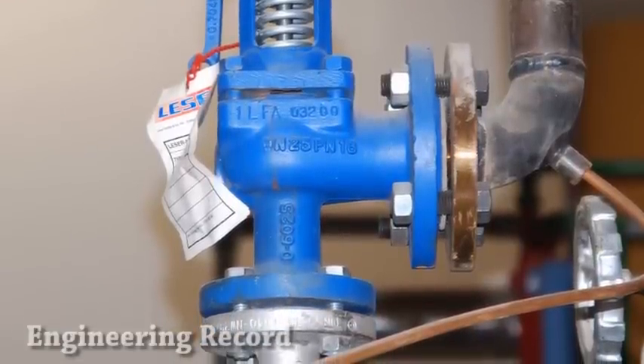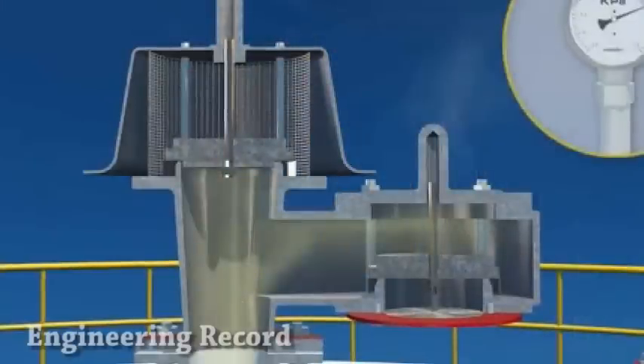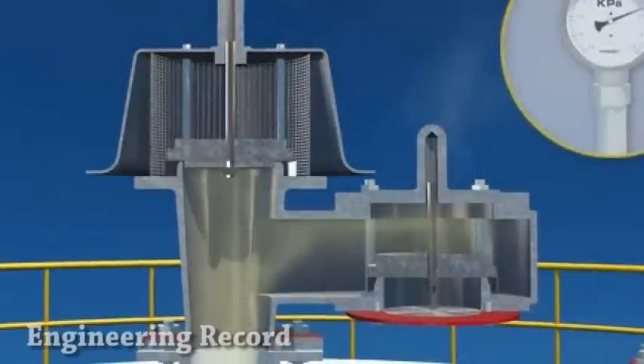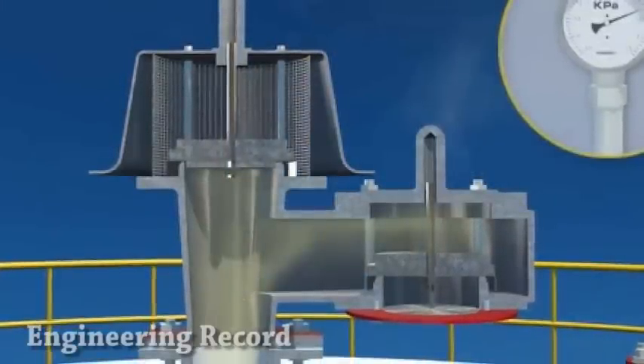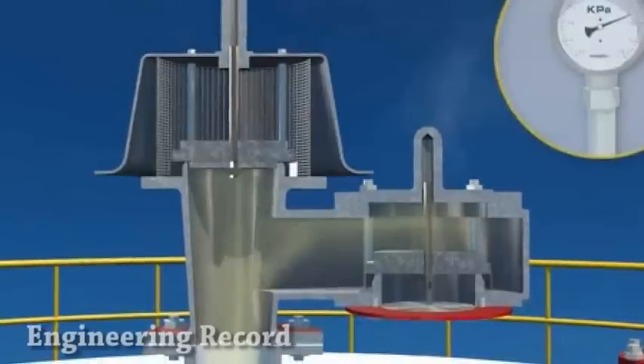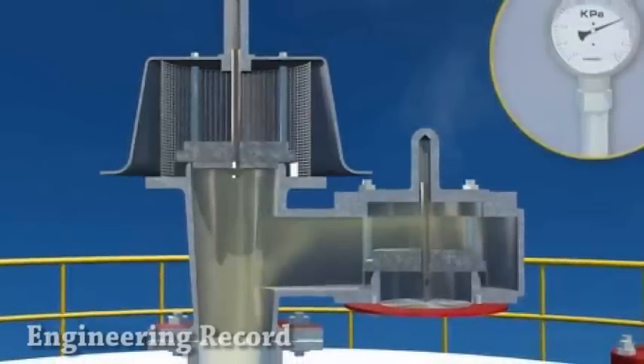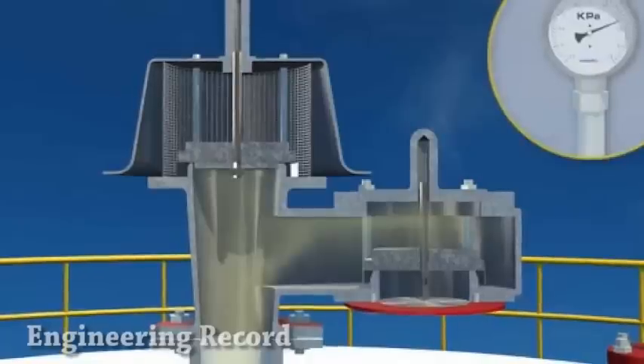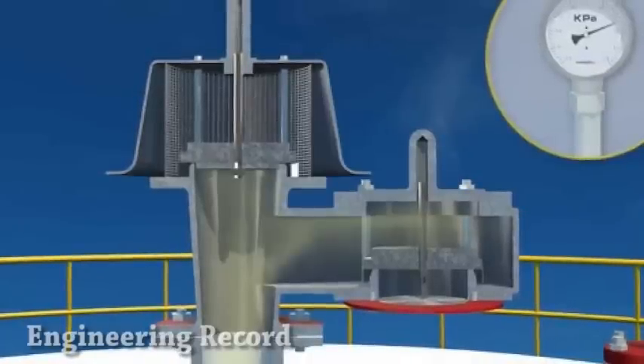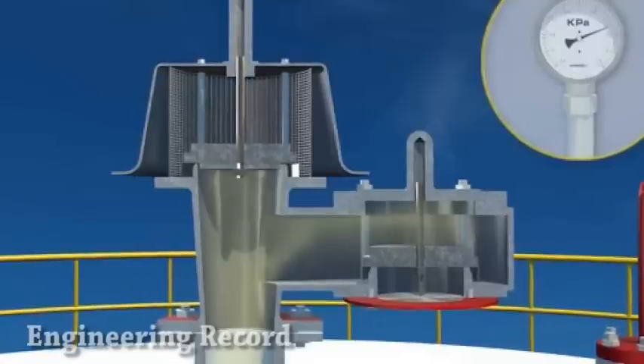In experience, if you need a valve for pressure safety in a separator, heater vessels, scrubber, or filter vessel, then you can call it a pressure safety valve, PSV. And when you need a valve for pressure safety in a storage tank, then you need a relief valve, PRV, or breather valve. Thus the explanation of the difference between PSV and PRV.